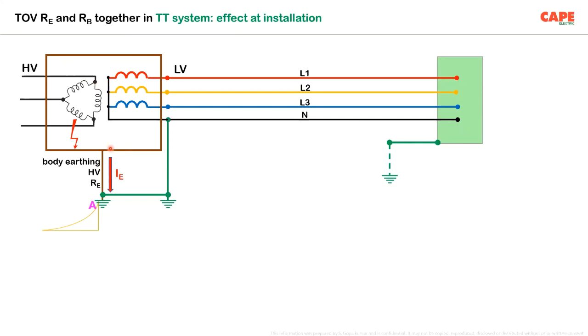You have a transformer from the public utility company. The body of the transformer, including the surge arrestor, is connected to an earth electrode. Then there is a neutral earth electrode. Both are interconnected or both are close by. Let's say, for example, both are maybe 1 meter, 2 meter away. So, electrically connected earthing of the high voltage system and the neutral of the low voltage system.